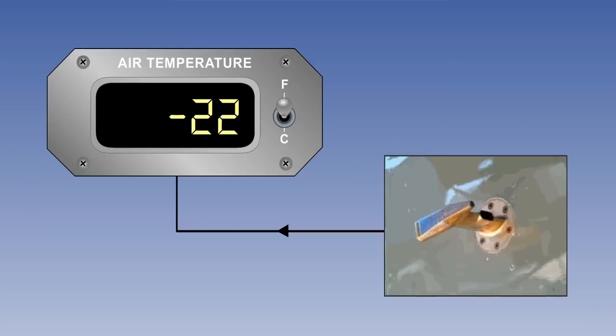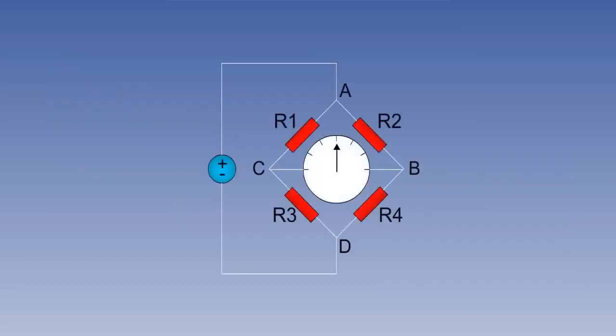It is often desirable to have temperature information in an electrical form so that it can be fed to other instruments and systems. Remote temperature gauges work on the principle that the electrical resistance of certain materials changes with a change in temperature. Measurement of electrical resistance will therefore be a measurement of temperature, and to measure it, a resistance circuit is employed, commonly known as a Wheatstone bridge.